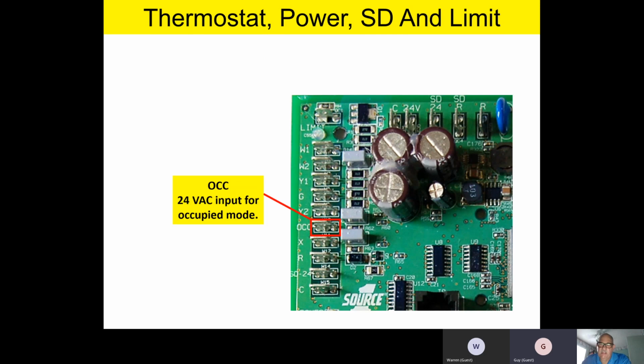That's a good question. So if you're getting an SD24 fault, and again, you have to remember that the trigger on that fault is not just open or close. Even though we, as electricians or technicians, when we think about an input to a board, a dry relay input, we think 24 to 27 volts, and when we think about an open circuit, we think 0 volts. However, the electronics on this board actually have a trigger voltage of somewhere around 18 or 19 volts. So if you've got 19 volts between SD24 and SDR, it may trigger the board as an open circuit. So I want you to catch this now.